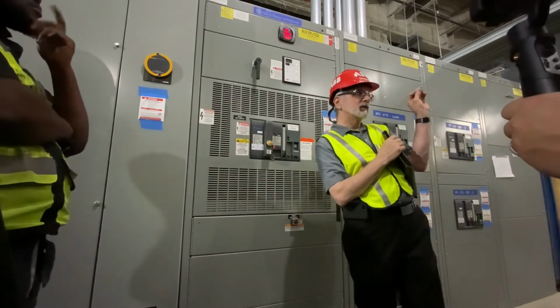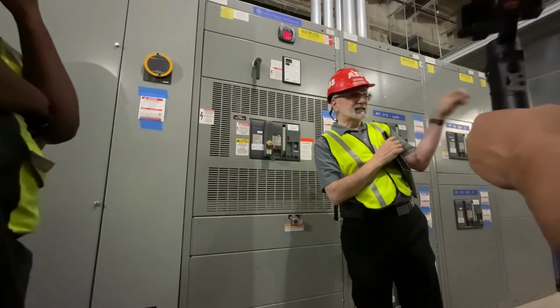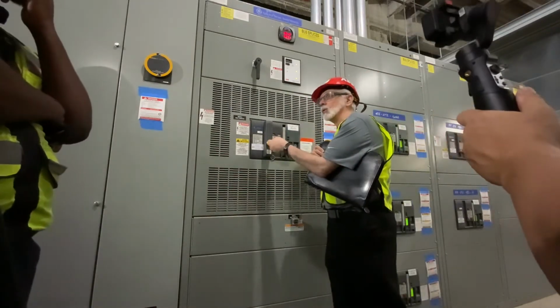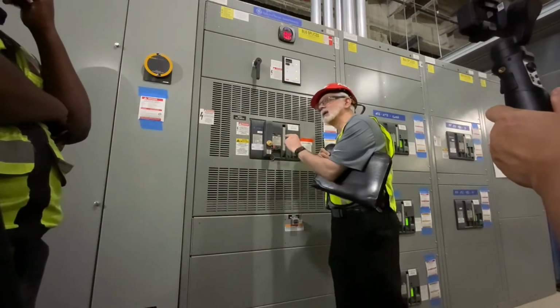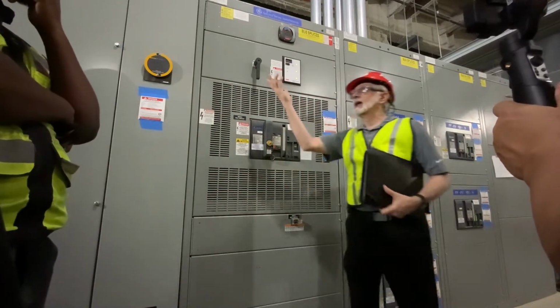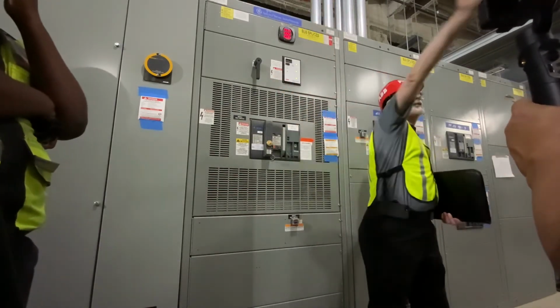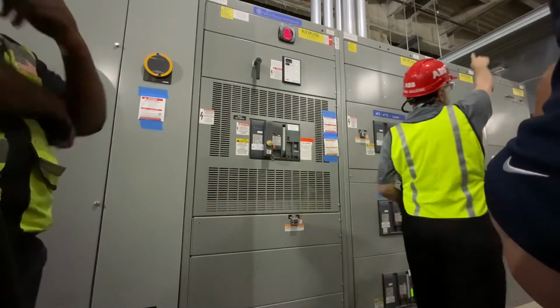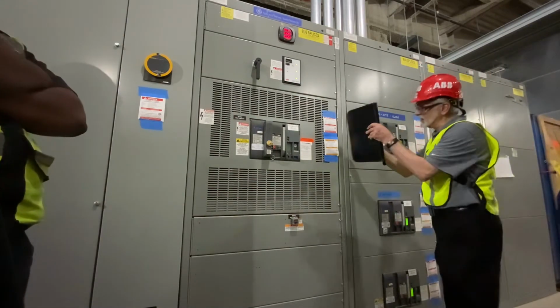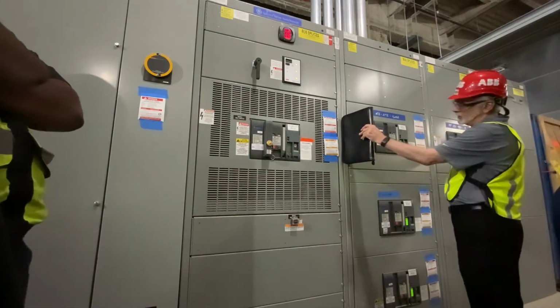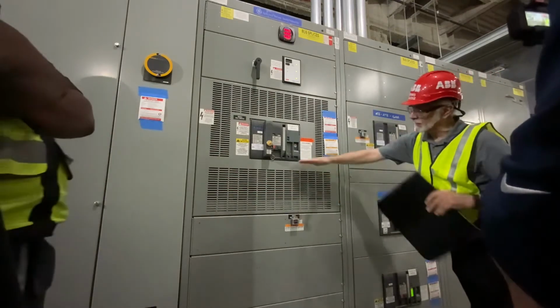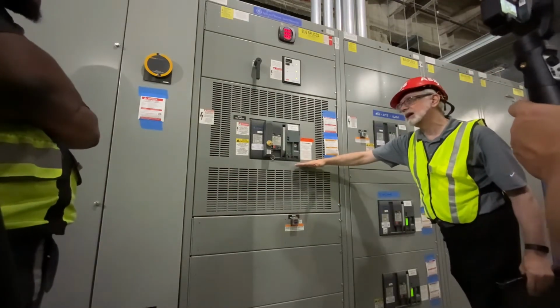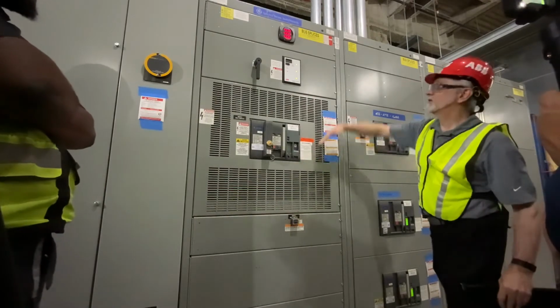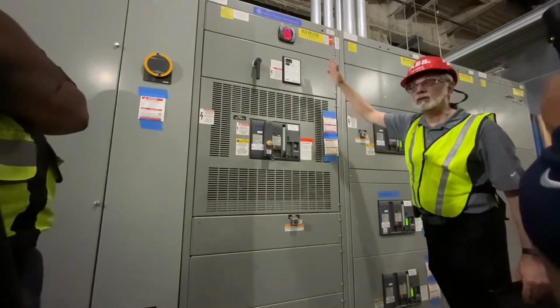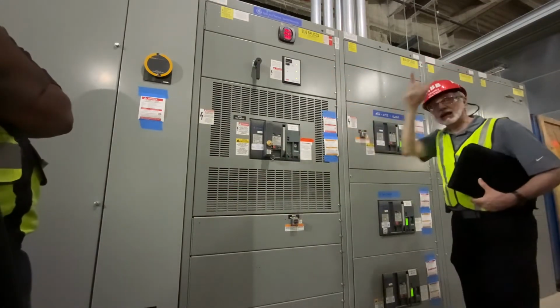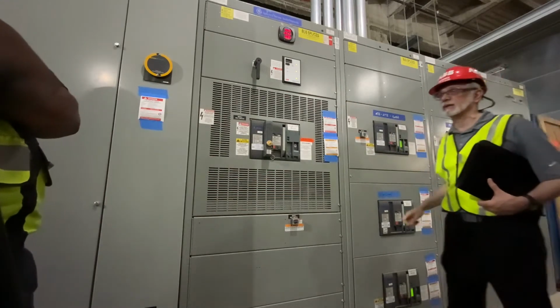I would go over to my tie breaker, stick the key in there, rotate it, which would allow me to then close my breaker. What would happen is the other substation through the bus tie would feed everything up to here, okay? So all the power would come straight up to the load side of this breaker, but from this side on, it would be dead, okay? And I would be feeding the line from the other side.